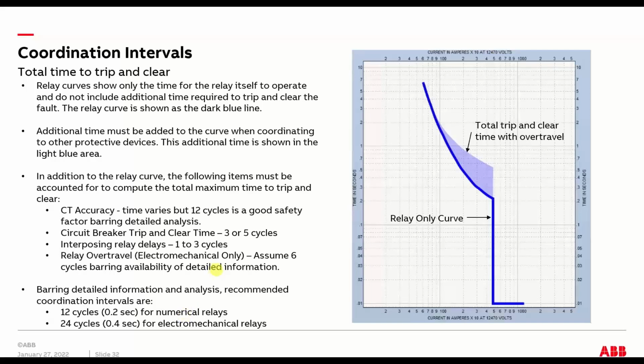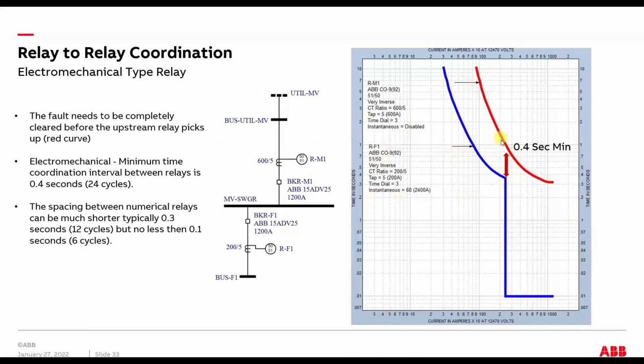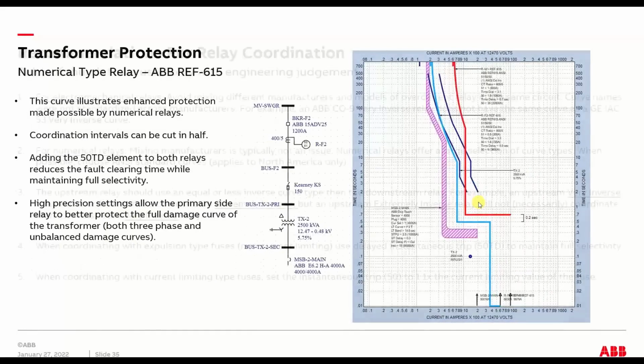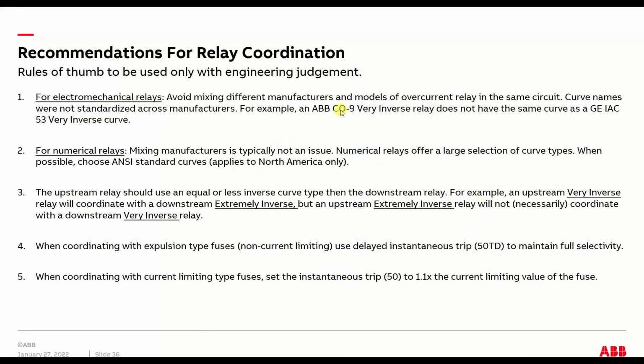So that's one of the big things that is different between doing relay coordination versus low voltage breaker coordination. This kind of further example, here's a downstream relay and an upstream relay. I'm just showing electromechanical, and I'm just showing you that's that minimum value you've got to set where your upstream relay is away from your lower relay. And that's all due to the speed of the breaker and the accuracy of the CTs and a whole myriad of design issues. Since we're running out of time, I'm going to speed through some of that stuff and just get down to some basic recommendations.